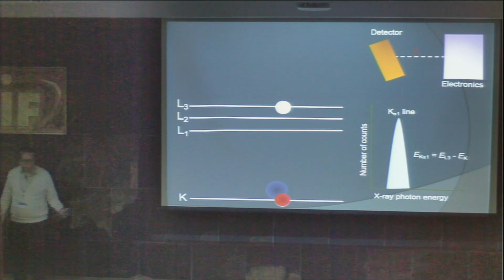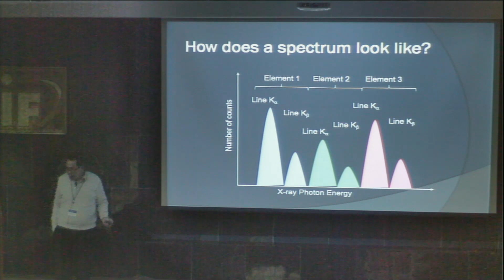When we have several elements in our target, we may have different lines. When we have the K alpha line, we usually also have the K beta line. We have 3 elements in this case, and we have the K alpha and K beta lines for each element, at different energies. These energies are characteristic of the elements, so we can identify them for quantitative analysis. Or if we have pure elements, we will have only these 2 lines.